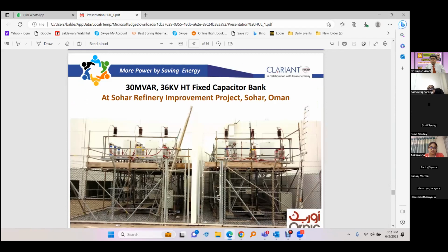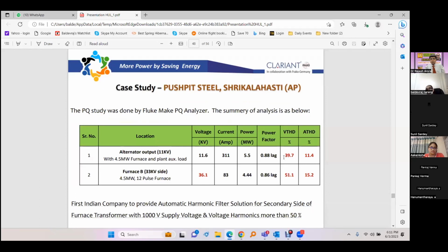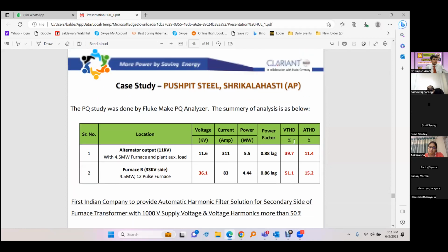And this is one plant where they had harmonics. It is a standalone plant, not connected to the grid. When they are connected to the grid, it is okay, they have no problems. But when they are running standalone, the system impedance is very high and a very small current harmonic results in a very heavy voltage distortion, about 40%. So they were not able to run the plant, and there were failures also, and the meters did not read at all because of this high voltage harmonic.